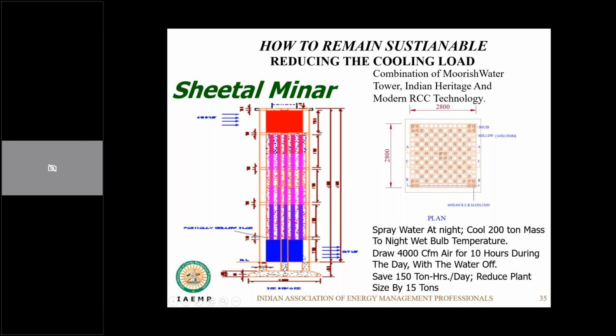Now, in the daytime, you stop the water spray, and you have this ambient fresh air coming in at around 40 degrees centigrade. As it comes in contact with the structure, which is overnight cooled to around 16 to 18 degrees centigrade, it loses its energy. The air cools down, but since there is no more moisture here, it is only sensible cooling. The cool and dry air then circulates into a naturally ventilated environment, open spaces and all that, or in certain scenarios it can be put across as part of a treated fresh air unit to your HVAC system, reducing its load.